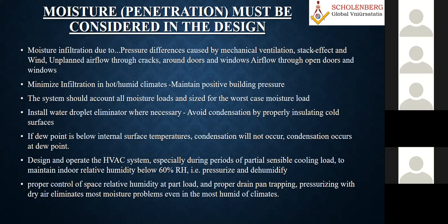If you do the psychrometric analysis, you can see the effect of moisture removal. Similarly, you have to also put the proper eliminators in the coil, with the supplier, in the AHU design. Otherwise, so much condensation will happen on the ducting side. And the ducts also have to be properly insulated.